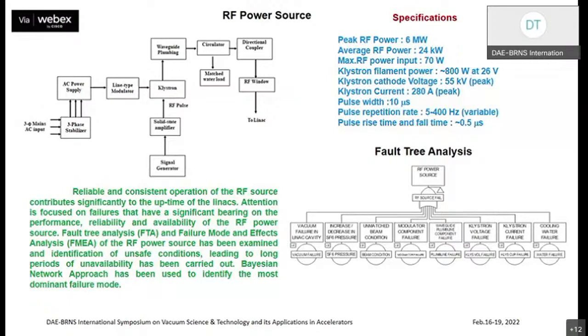The aim of this study is to study the faults in these systems. Various faults are indicated here in the fault tree, which covers vacuum failure, increase or decrease in the SF6 pressure, which can lead to breakage of the tube in case of increase, and electrical breakdown in case of decrease. So you have various faults contributing to the power failure of the RF power source.